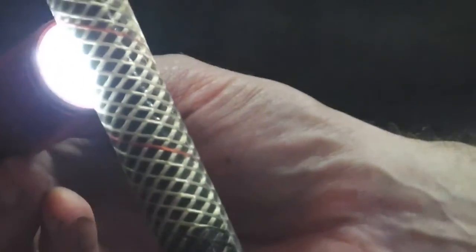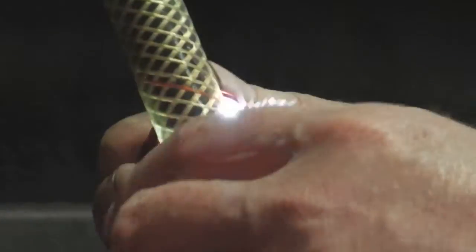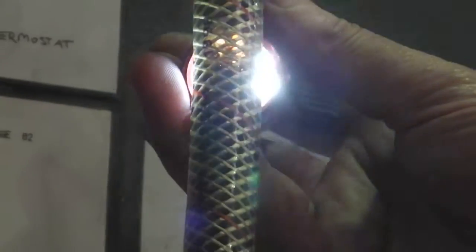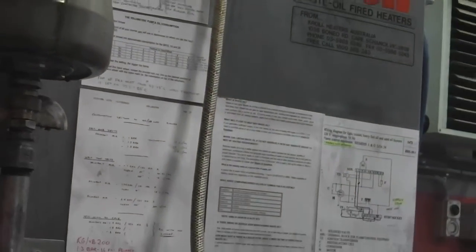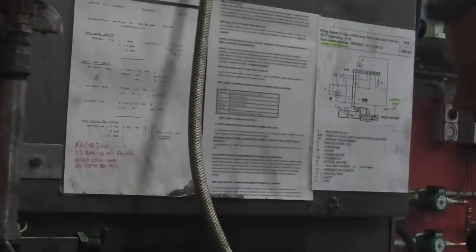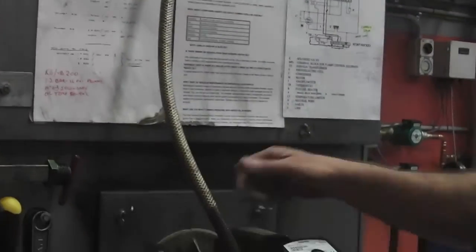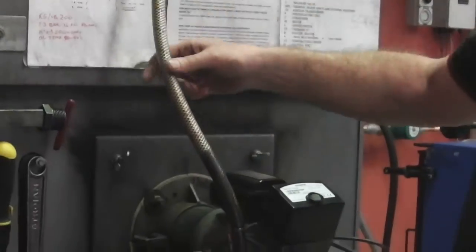The best thing to do is have a cheap torch sitting nearby to see if you can get that in the shot, that there is, in fact, oil present in this degassing pipe. The top of the oil here will always be at the same height as the day tank level. Our day tank is pretty much on about five foot on that level there. So that's the degassing pipe.